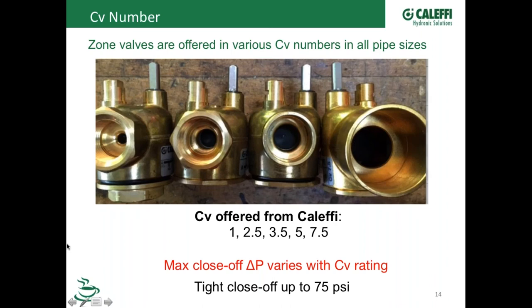So we did that to make it nice so you can have a large diameter pipe going in without a bunch of adapters, but going to a larger diameter connection size doesn't give you a higher flow rate through that valve. That's still a 7.5 CV valve, even though you could put a pipe on that that could flow 19 gallons a minute. So what you want to do in that case is use, there's charts online. We've got a little Excel cheat sheet that we can mail to you, where you put in the CV of the valve and the gallons per minute through that valve, and it will tell you what kind of flow you're going to have going through that.